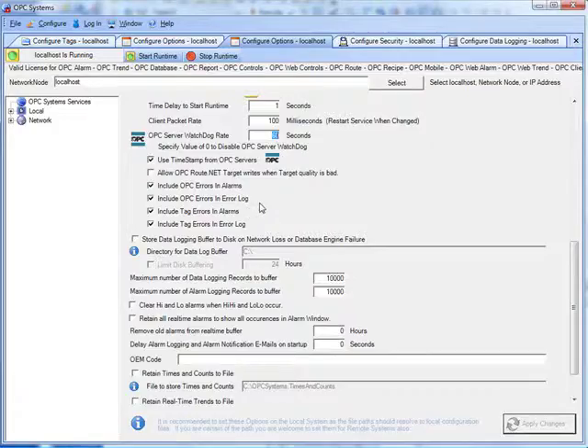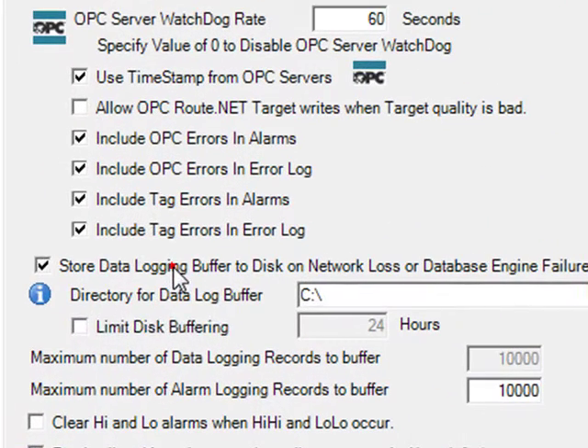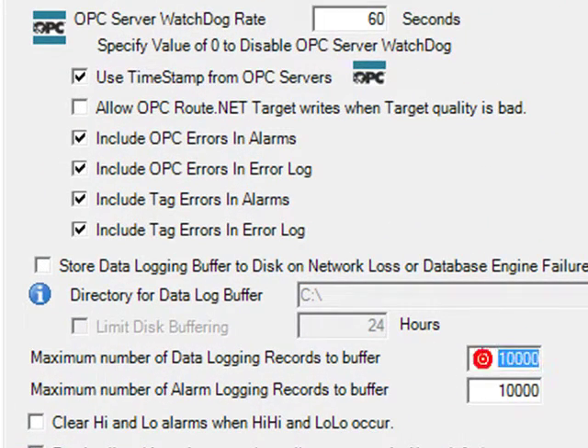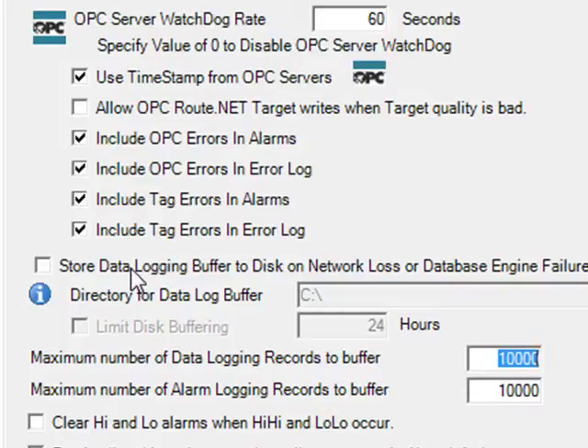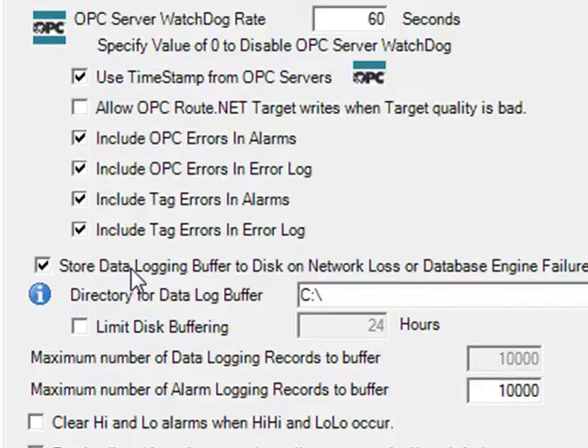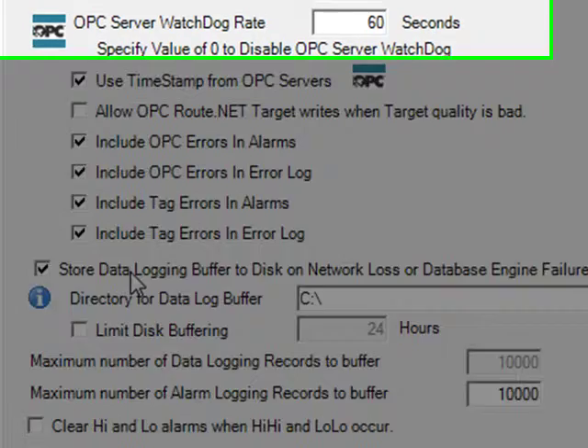Under Configure Options is a property to store data logging buffer to disk. By default, it uses RAM of up to 10,000 records. But if we choose the option to store data logging buffer to disk, you are then only limited by the amount of hard disk space of where you plan to do the data buffering during the temporary network loss or database engine failures.